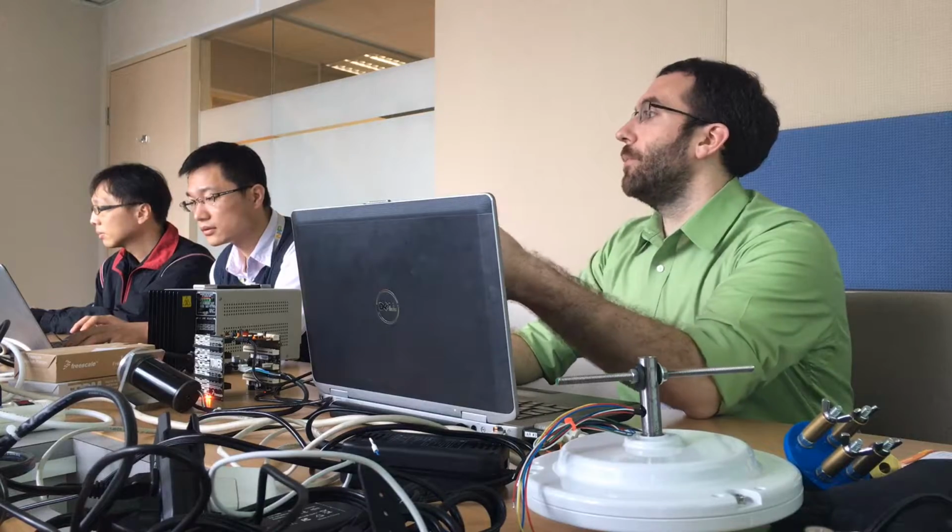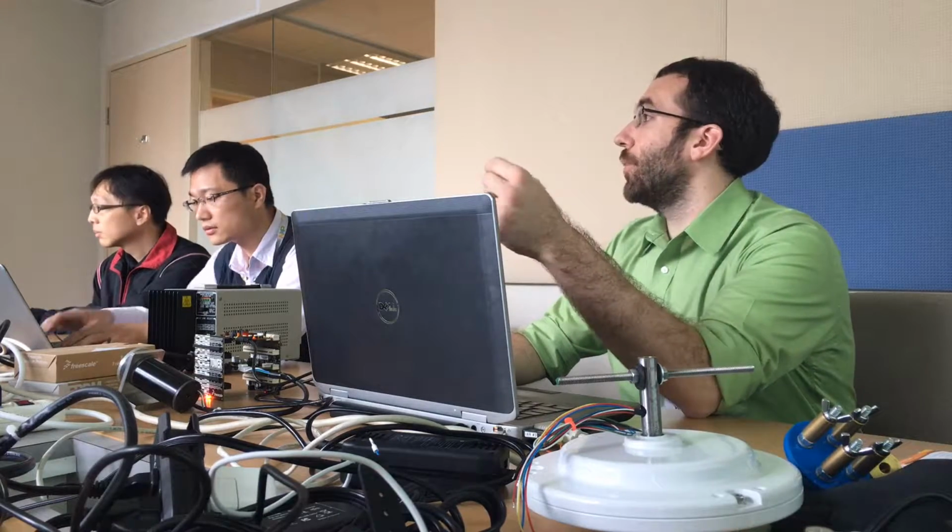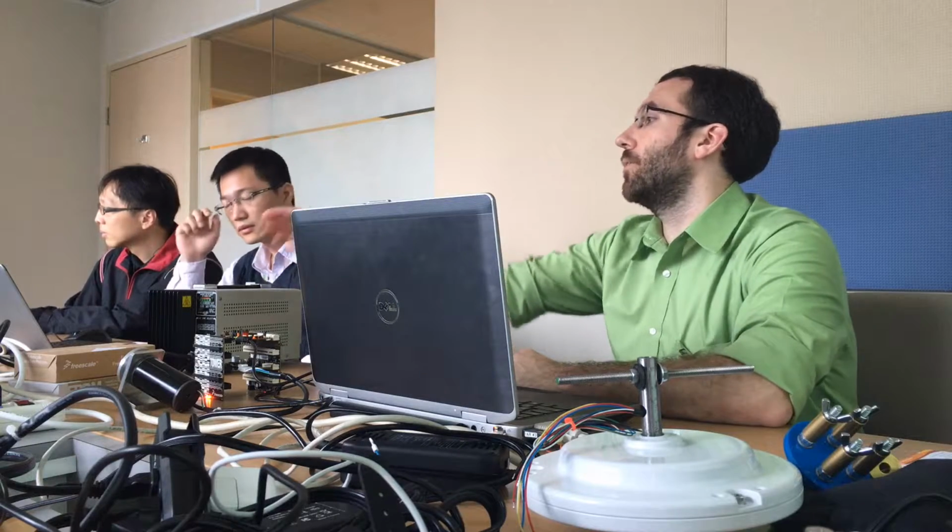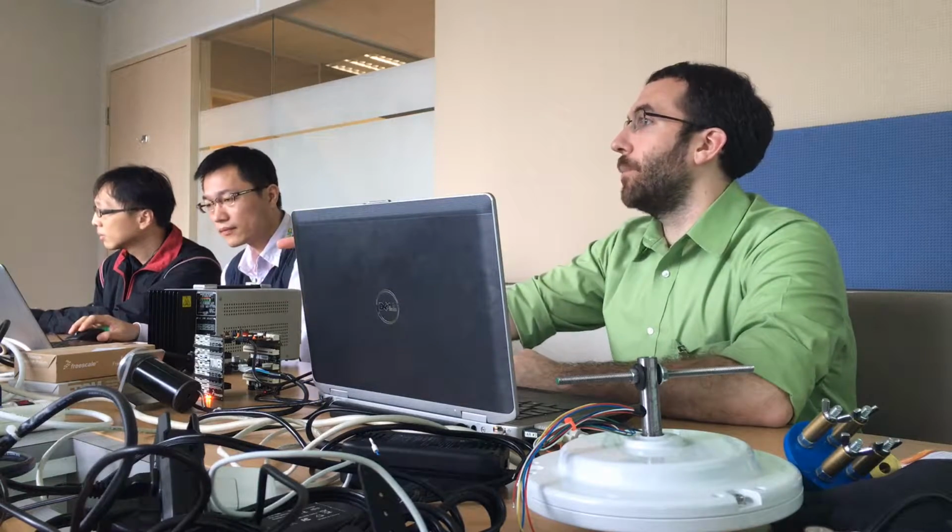If your motor's rated speed is less than 4000, I would set it to whatever your motor's rated speed is. I know the compressor motor is rated for 3000, so I wouldn't exceed 3000 because of the mechanics attached to it.